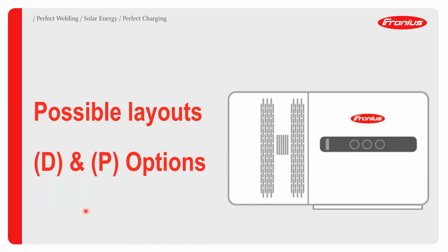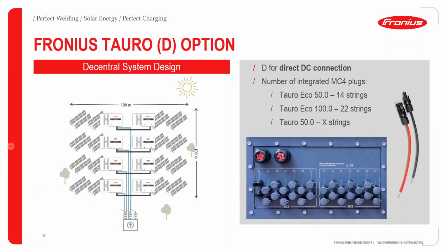So let's look at these layouts that are possible with the Tauro inverters. As I've mentioned before, we can talk about a D or P option, the D standing for the direct option, and the P standing for the pre-combined option of the Tauro series of inverters. So with the D option, this is the decentralized design or the decentralized topology. As I had mentioned before, all the strings are collected directly into the inverter, and then from the inverter, you do daisy chaining depending on the size of your installation. And then from a 200 kilowatt block, that means either 2 by 100 kilowatt Tauros or 4 by 50 kilowatt Tauros, you can achieve daisy chaining.